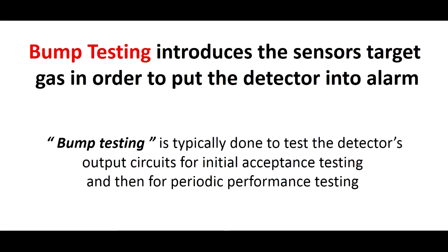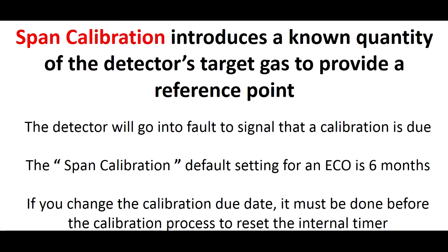Bump testing is typically done to test the detector's output circuits. This would be for alarms, faults, and facility equipment such as emergency exhaust fans. Span calibration introduces a known quantity of the detector's target gas to provide a reference point.